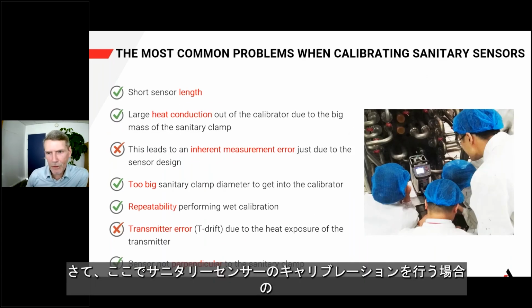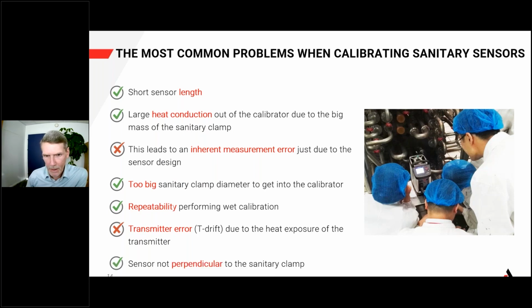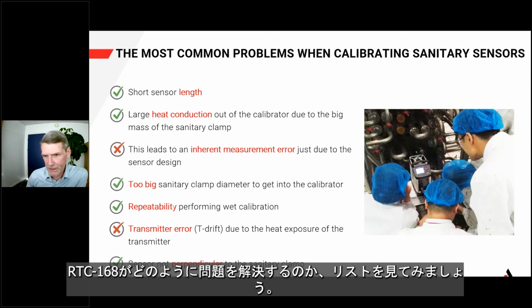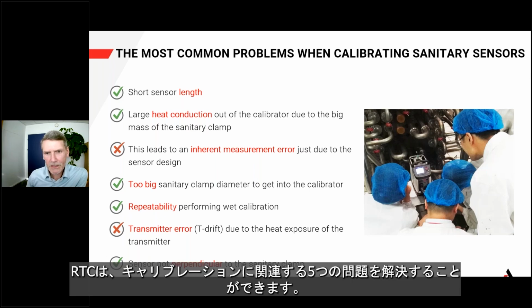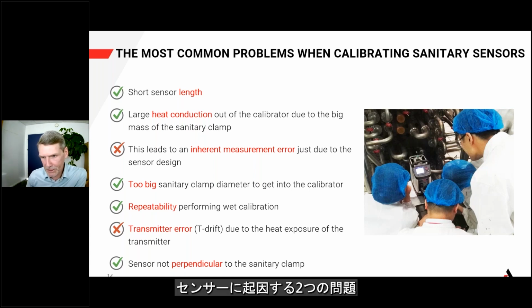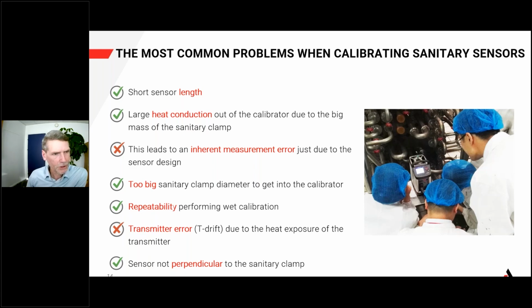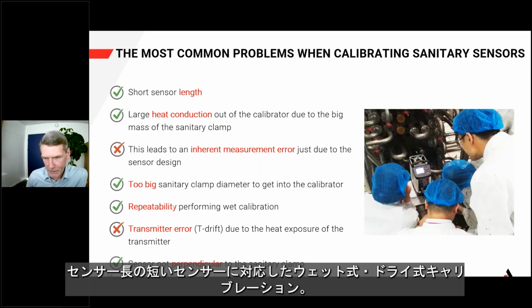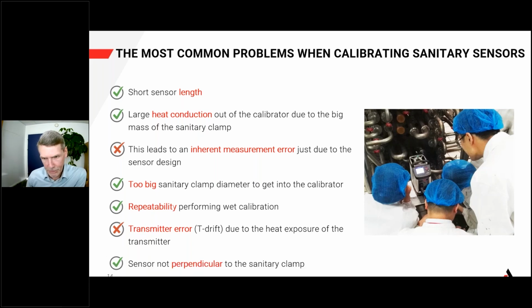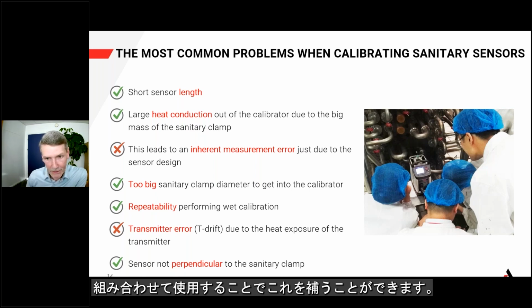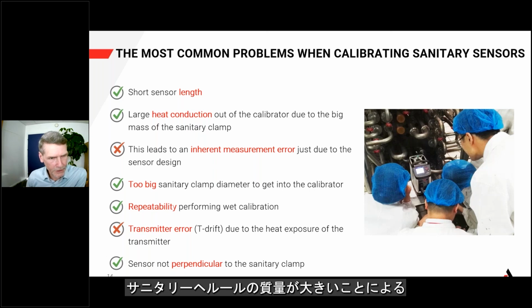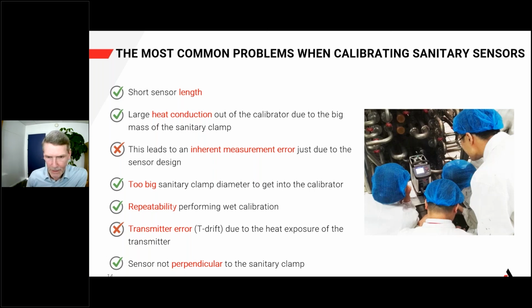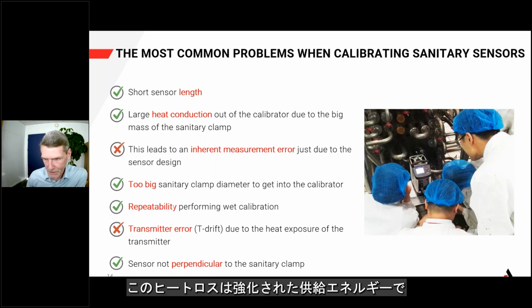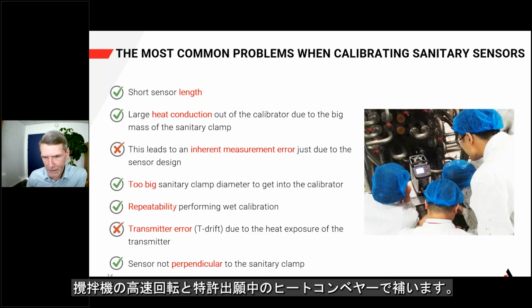Now we are back to the list of common problems when calibrating sanitary sensors. Let's go through the list and see how the RTC168 solves the problems. The RTC can solve the 5 calibration-related problems. Only the 2 problems coming from the sensor design can naturally not be compensated. Short sensor length. For both wet and dry calibration, this is compensated by using our short reference sensor positioned at the same depth as the sensor under test in combination with an active top zone temperature control. Large heat conduction out of the calibrator due to the big mass of the sanitary clamp. This heat loss is compensated by enhanced energy, fast stirrer speed, and the patent-pending heat conveyor.